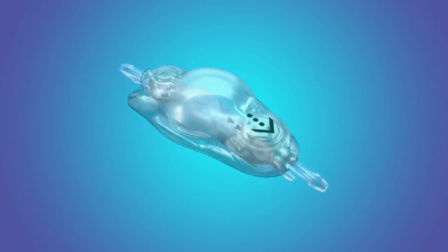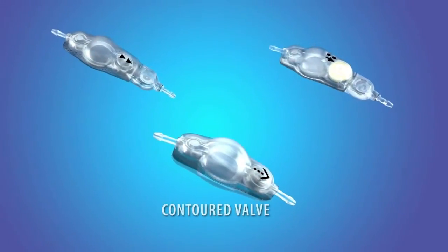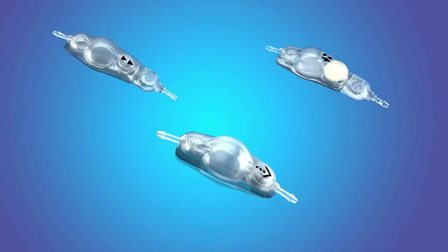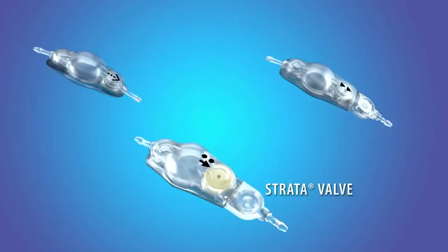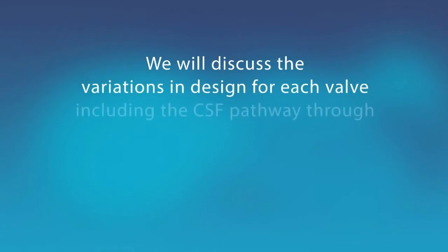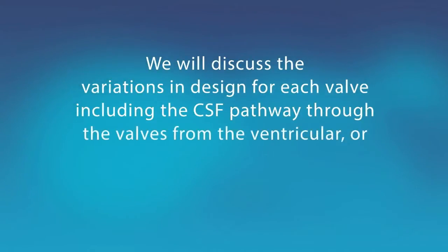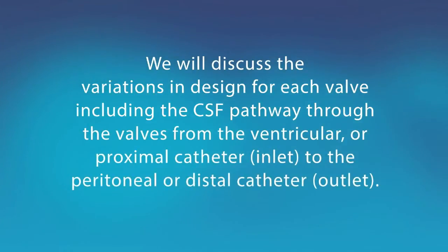In this video, we will cover the three types of Medtronic valves used for the treatment of hydrocephalus. The first commercial Medtronic valve was the contoured valve, now a part of the CSF flow control valve family. Subsequent to this was the delta valve with a siphon control device called the delta chamber, and most recently was the strata valve with adjustable pressure capabilities. We will discuss the variations in design for each valve, including the CSF pathway through the valves from the ventricular or proximal catheter inlet to the peritoneal or distal catheter outlet.